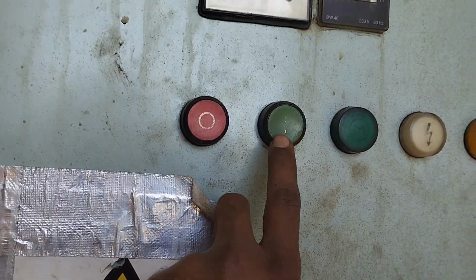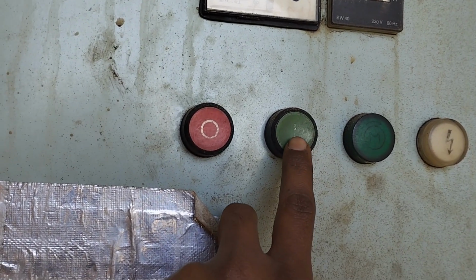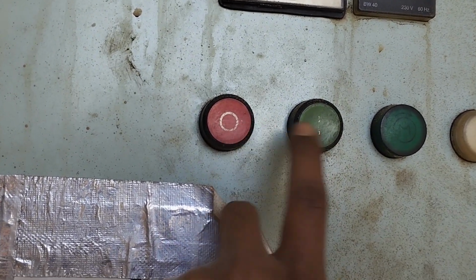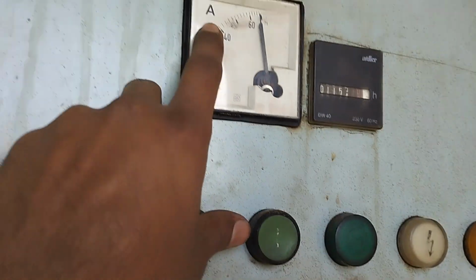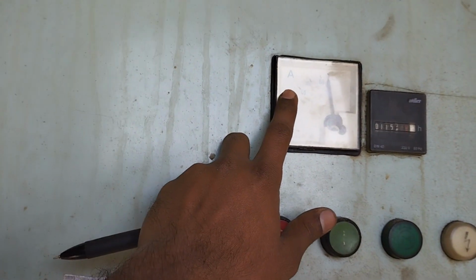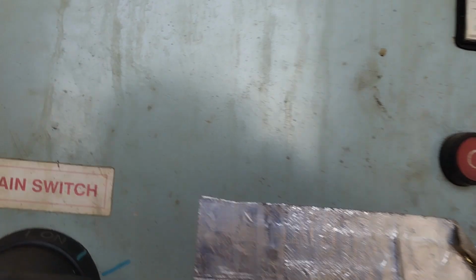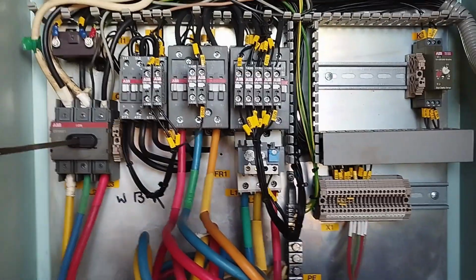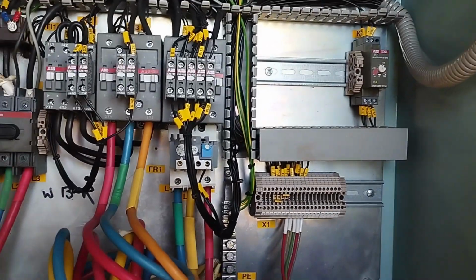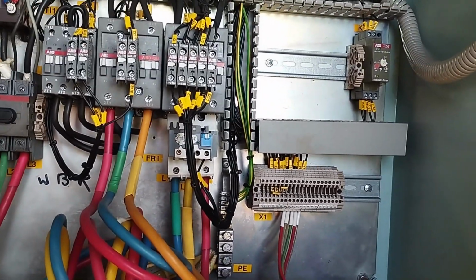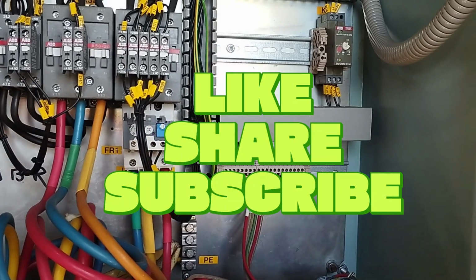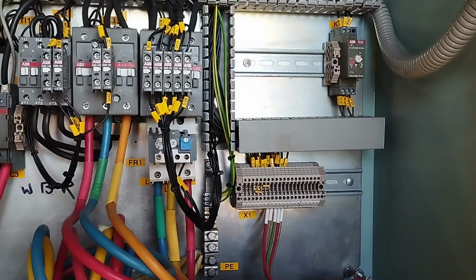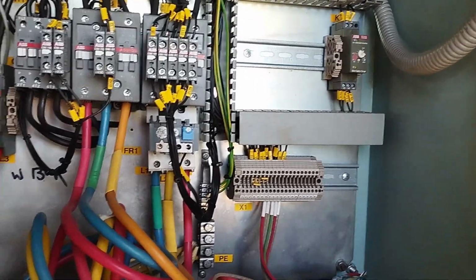So this is the start stop push button that I explained, local start and local stop. This is the indication, and this is the meter showing how much current the motor is drawing. So in this way you can see this is a very basic and very useful circuit diagram for troubleshooting. It is very important for troubleshooting. If you know the circuit diagram, you can easily troubleshoot the provision crane in case of emergency, and also in normal routine.